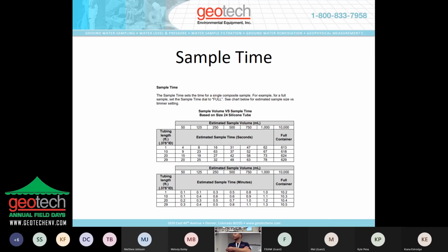Maybe something to consider - what about other ones that you've used, do they do a back flush prior to starting a second sample? Most of them do it the way your system does it, but if you're dealing with some sensitive low concentration parameters, you may want to purge the line before you take the next sample, to get a more representative sample, but I don't think it really matters that much.